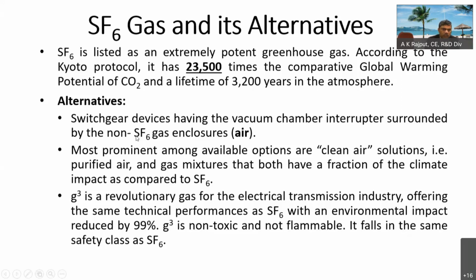So there are two or three types of development which ABB has also shown. The ABB expert has just shown switchgear devices having a vacuum chamber interrupter surrounded by non-SF6 gas enclosures, that is, compressed air, pure compressed air. And he rightly mentioned that it should be dry air. It should not contain moisture. So that adds a cost to it, making the air completely dry.